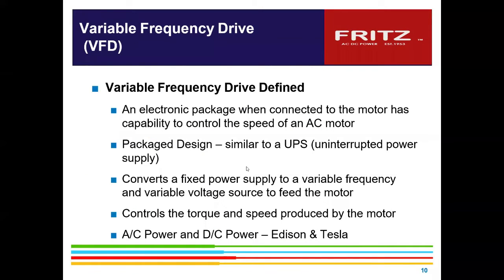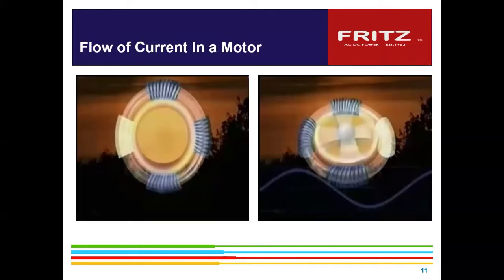So what the variable frequency drive is, basically, is an electronic package which connects to the motor and has the capability of controlling that AC motor. They're designed similarly to power supplies and utilize transistors. They convert that fixed speed supply to variable speed, and you can then control the torque and speed of the motor, where prior to that the motor ran at one speed.